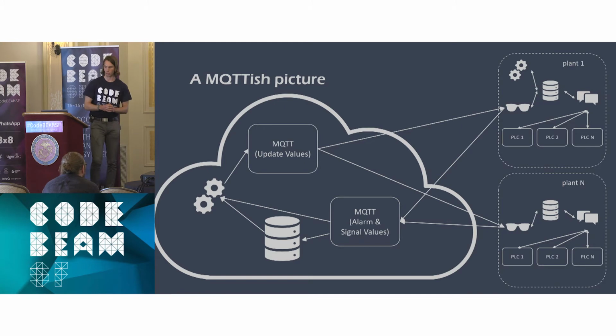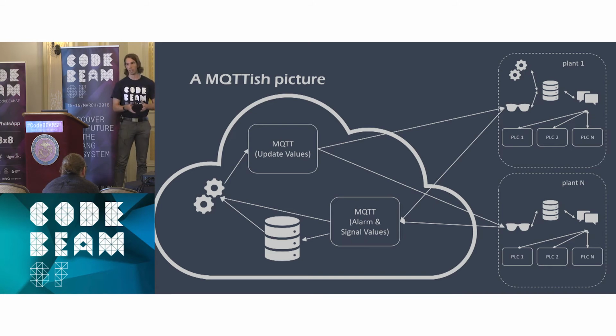And yeah, as you will soon see, there is a lot of different sensor data going from left to right and everywhere. And that's why we have selected to use the MQTT protocol to send this data from one plant to the cloud and from another plant to another cloud. And we use different brokers to separate the permissions to update set points for plants, or just to read the data, also subscribe to sensor data or alarms. So for all of the plants we have this agent and local storage for buffering data or redundancy of data. And then we have this gateway or communicator which talks to the PLCs, which are wired or connected to the pumps or valves or compressors or fans, or another IoT device.